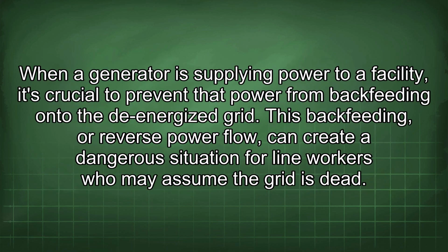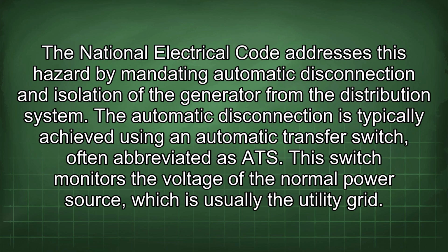When a generator is supplying power to a facility, it's crucial to prevent power from backfeeding onto the de-energized grid. This backfeeding, or reverse power flow, can create a dangerous situation for line workers who may assume the grid is dead. The National Electrical Code addresses this hazard by mandating automatic disconnection and isolation of the generator from the distribution system. The automatic disconnection is typically achieved using an automatic transfer switch, often abbreviated as ATS.